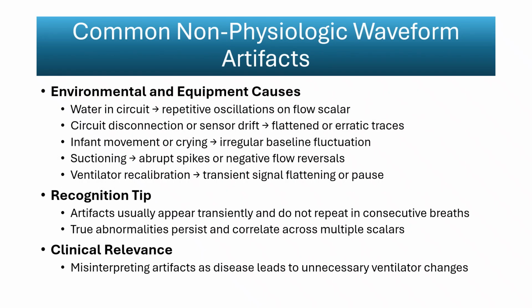Waveforms do not always reflect lung physiology. Many disturbances originate from the circuit, ventilator hardware, or infant movement. Recognizing these artifacts prevents misinterpretation and unnecessary ventilator adjustments. Circuit water is a frequent source of repetitive oscillations on the flow scalar. Even a small amount of condensation can move with each breath and create rhythmic perturbations that resemble patient effort. Sensor drift or partial circuit disconnection flattens or distorts the scalars because the ventilator loses accurate reference points for flow or pressure. Movement has a large impact in neonates.